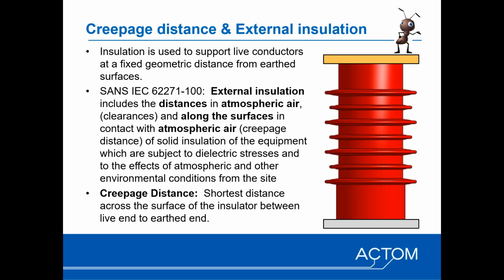Moving then on to external insulation and creepage. The insulation material is used in the form of post insulators or support insulators to fix or support live conductors in a geometrical position between live and ground. IEC 62271-100 defines the external insulation, which includes distance in atmospheric air, in other words, clearances between phases or between insulation or electrodes, as well as the distance along the surface in contact with atmospheric air. In other words, creepage across the surface.